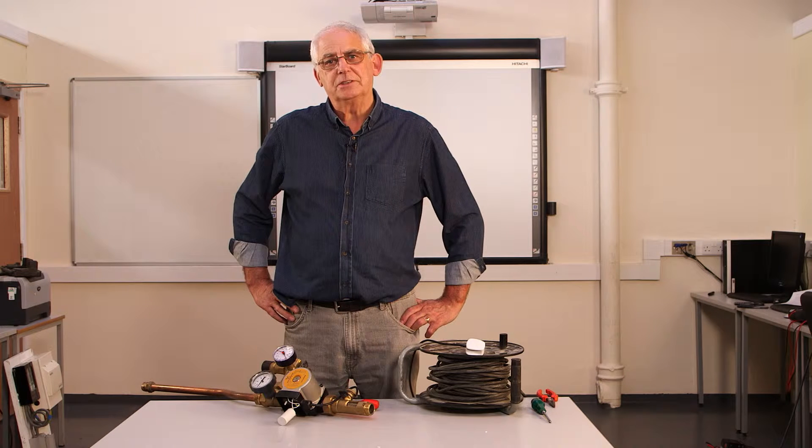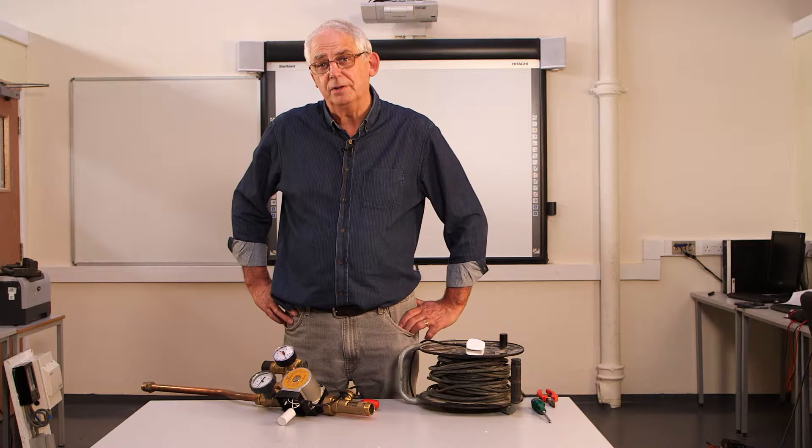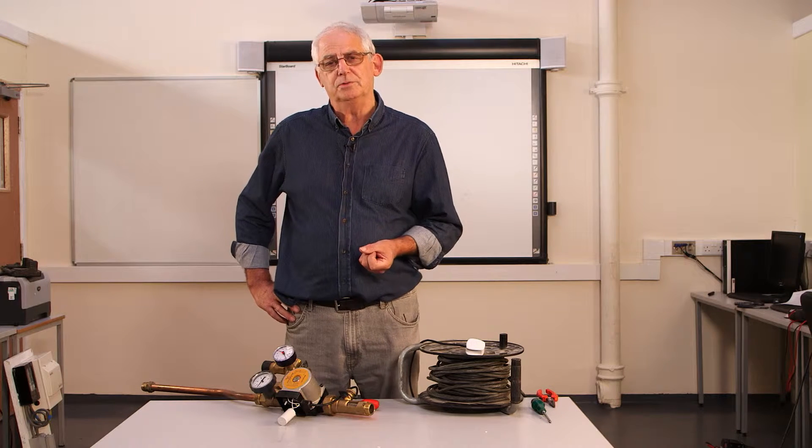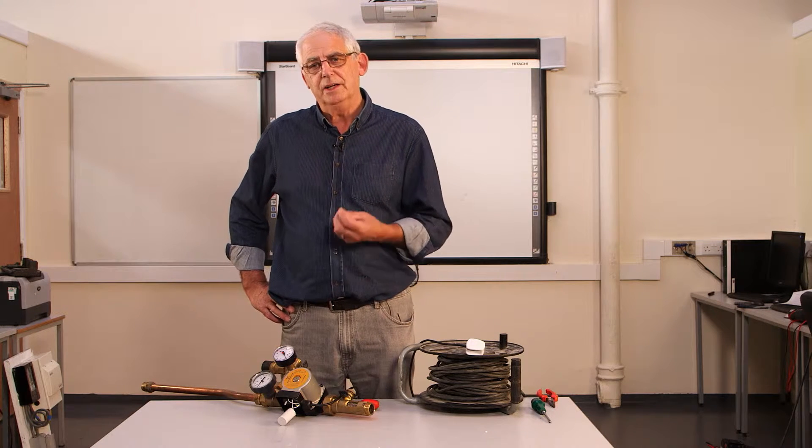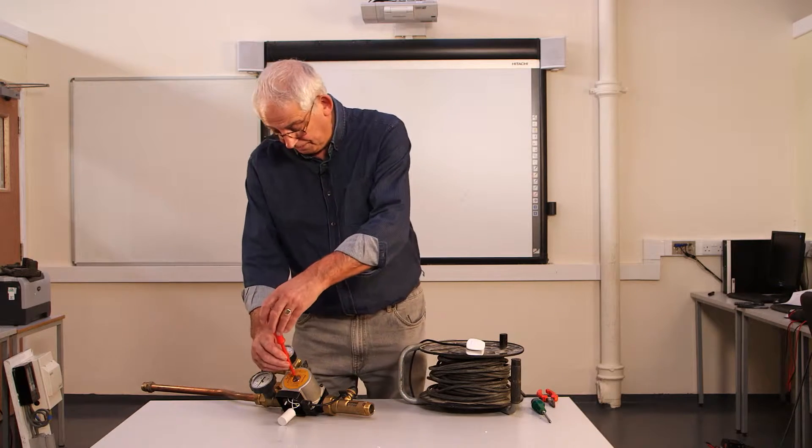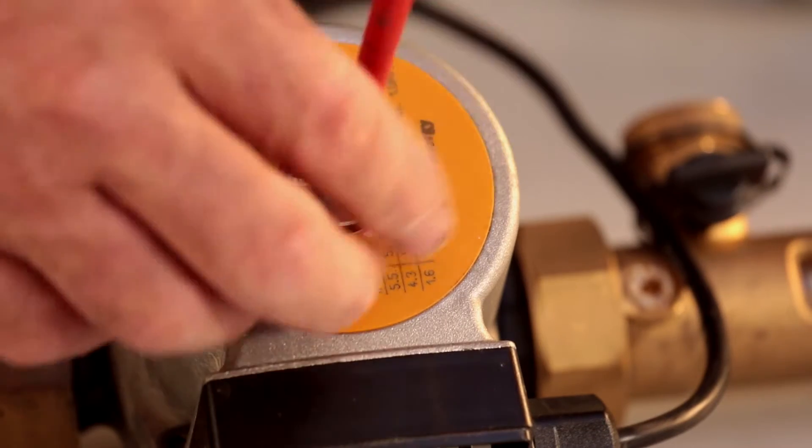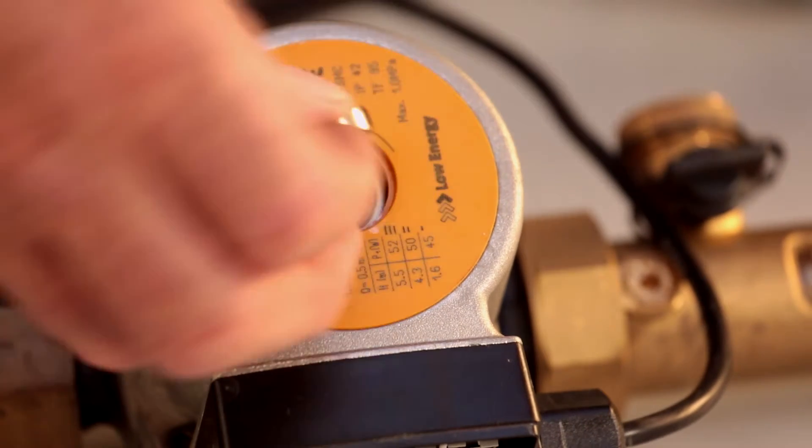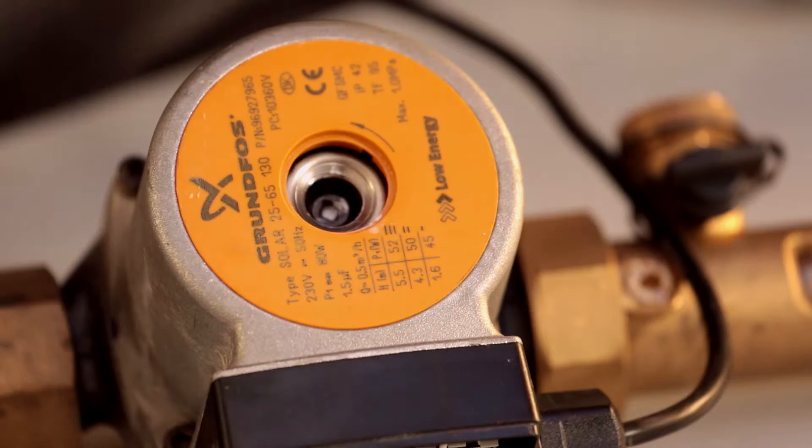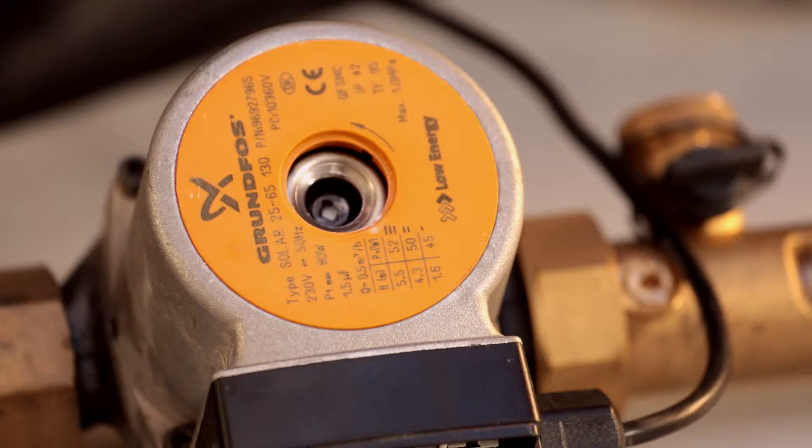Very often it's because they've been standing still during the summer months and the bearing and the seals have just corroded slightly and the motor stuck. Really all it needs is for the top of this to be taken off, give the spindle inside a little twist and the motor will run perfectly well.